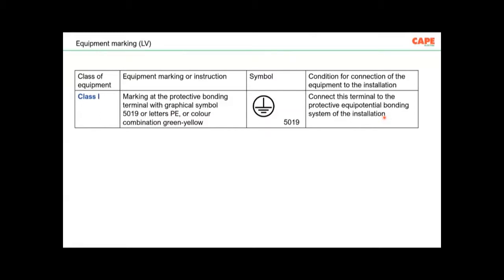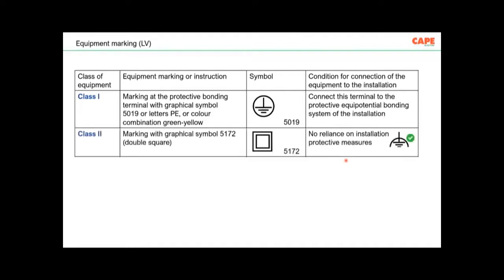So equipment earthing is very simple. You have a terminal in your equipment, you take a wire and connect that equipment to the equipotential bonding system of your installation. Then we go to the second type of equipment, which is class 2. Class 2 is an equipment having double insulation. It means whenever there is a fault in this equipment, the exposed metallic parts are not going to experience a shock voltage. So these are shock-free installations or shock-free equipment. For example, a 2-pin equipment with a 2-pin plug, such as a video receiver or audio video equipment which we use in our home. Some of those equipment will have this kind of symbol.